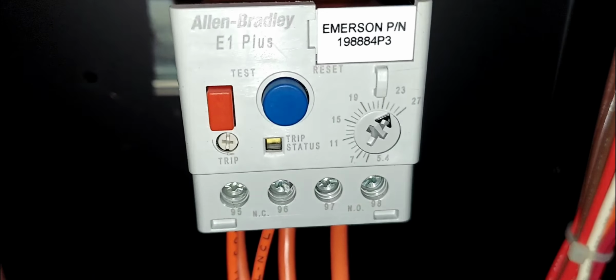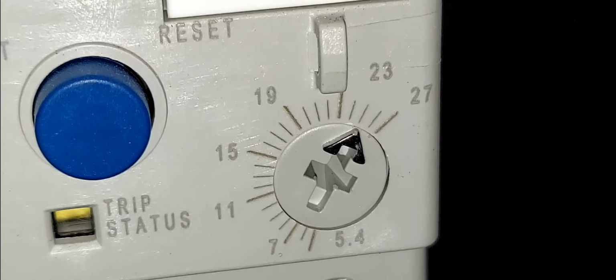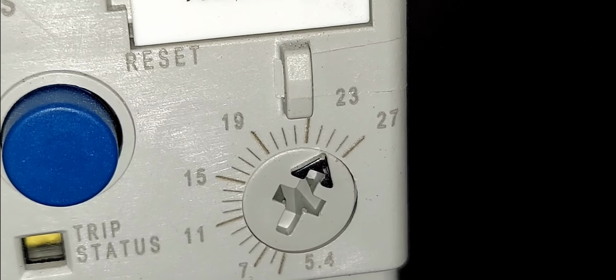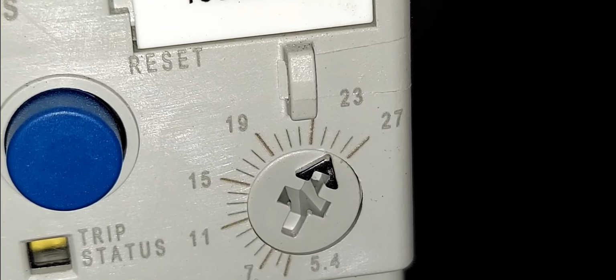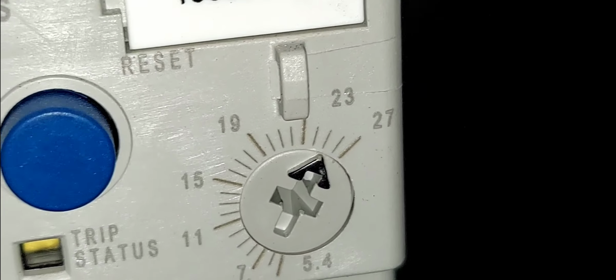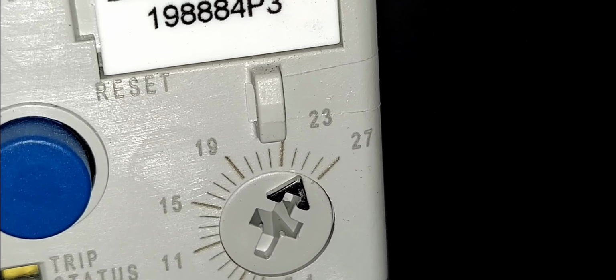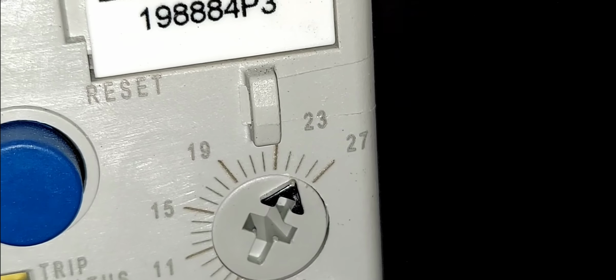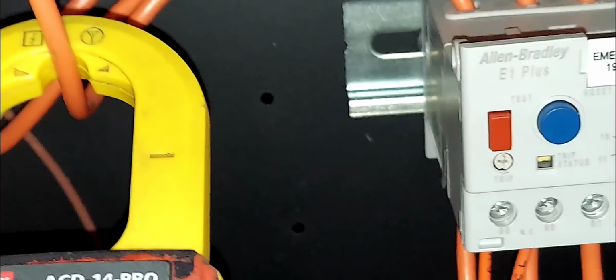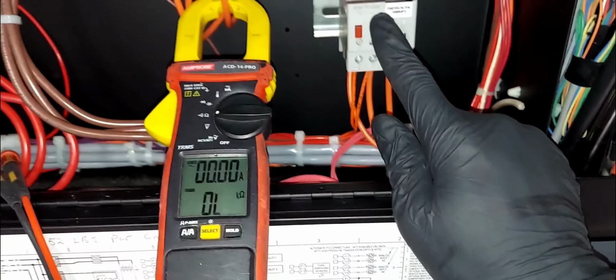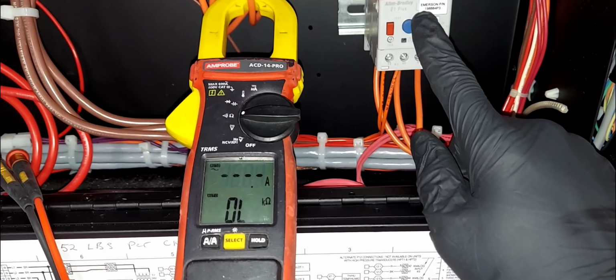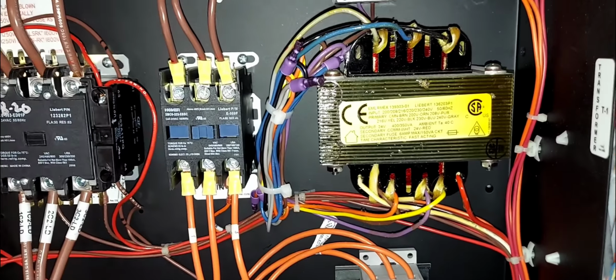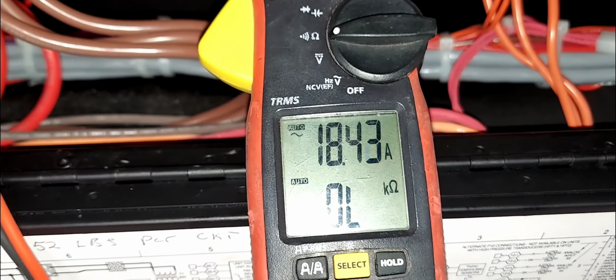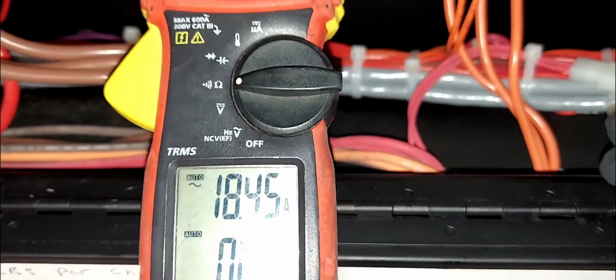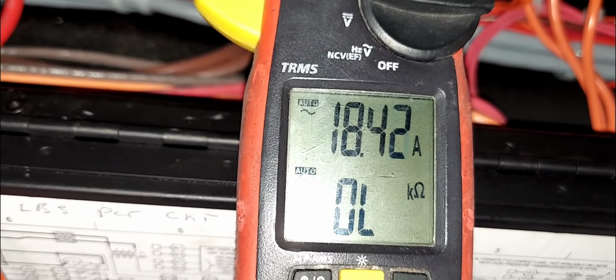Currently, this dial looks like it's set for 25 amps. It's like 23, 24, 25, 26. Yeah, 24 or 25 amps, somewhere in that neighborhood. So I really don't know what happened here, guys. Why the overload tripped, because it's only running at 18.5 or 18 amps.